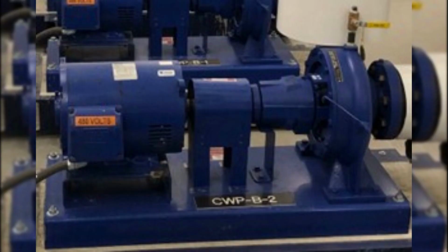For execution and installation, pumps must be mounted on vibration-isolated concrete inertia bases and aligned carefully within the manufacturer's tolerances. The contractor has to make sure that proper service clearances are maintained, so the pumps can be accessed and serviced in the future without major disruption. On the electrical side, all power wiring is the responsibility of Division 16, the electrical contractor. Meanwhile, the control and interlock wiring must be handled by the temperature control contractor, or TCC.